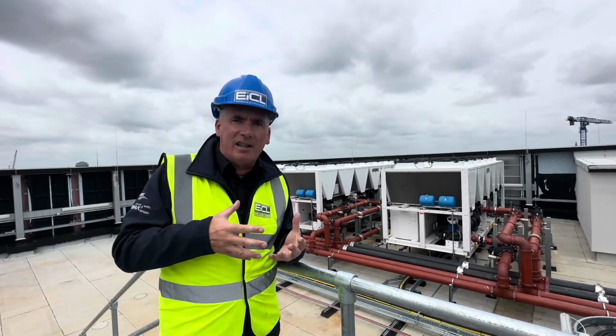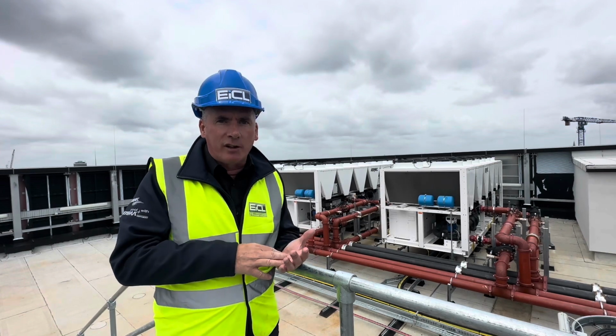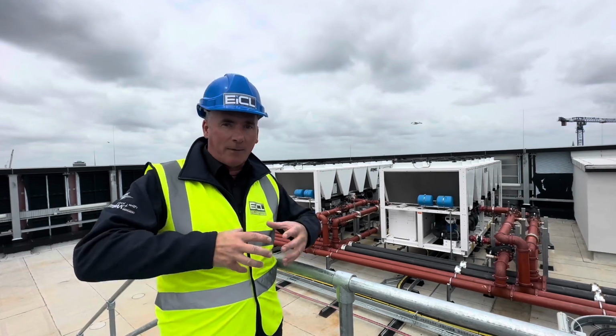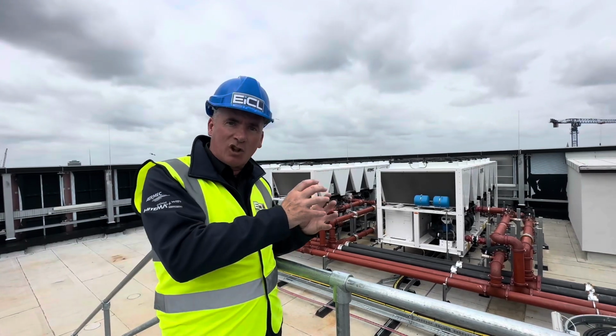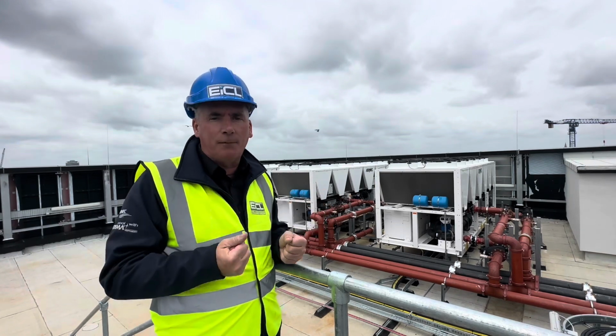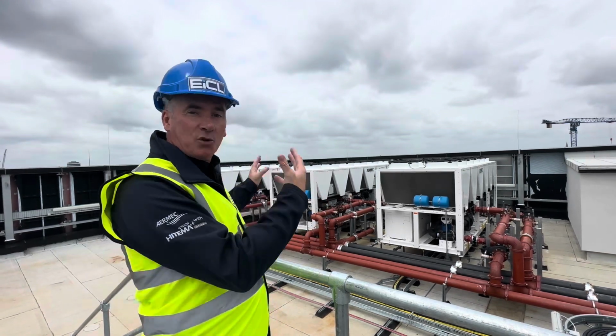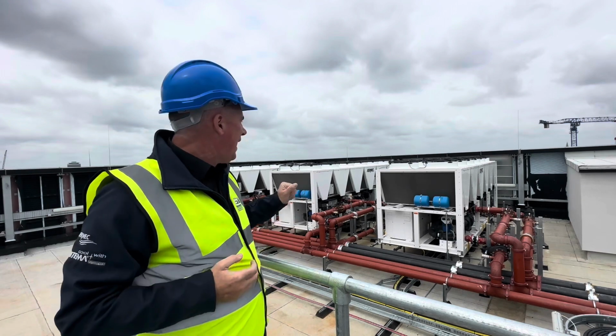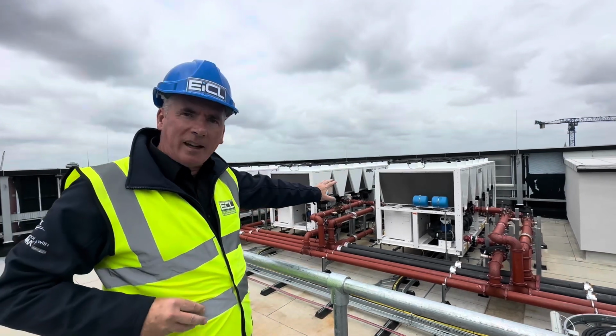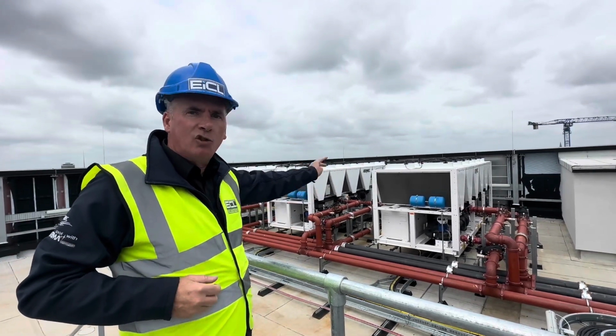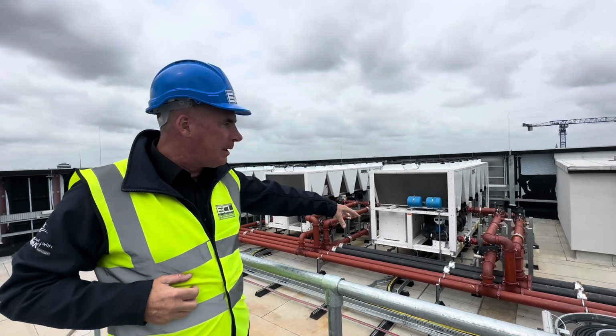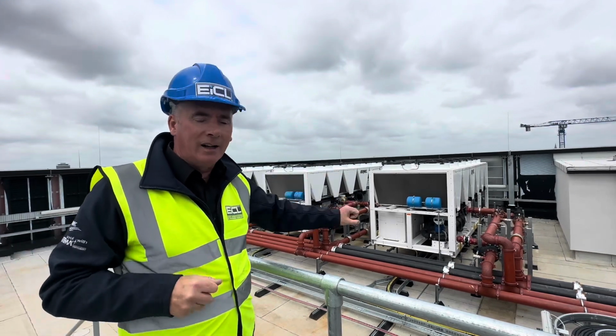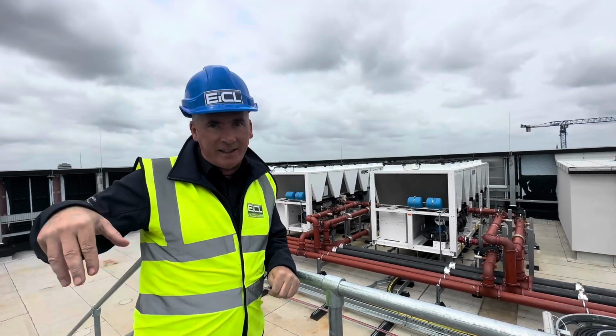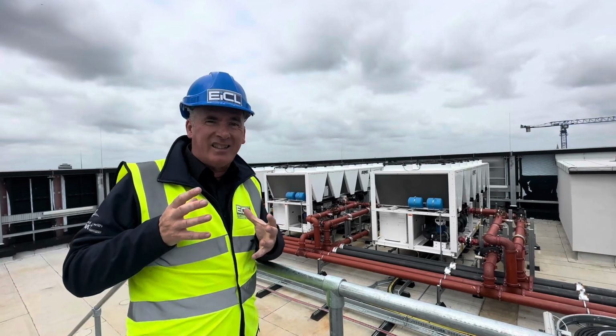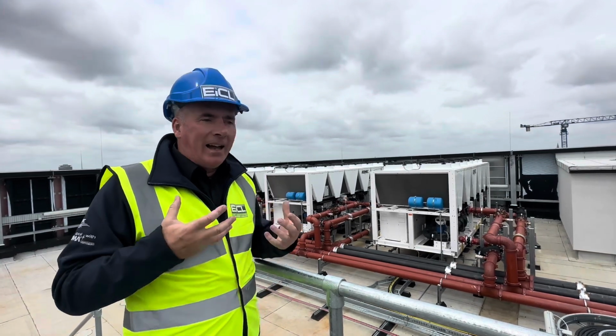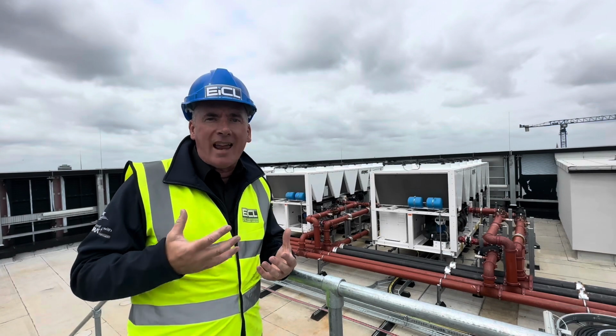A lot of people are used to seeing these on schematics and linear drawings, and we often do schematics where we have a blue beam, where we have the image incorporated, again to try and bring the schematic to life, whereas you can actually physically see what they're like here now. So normally three of them are connected in parallel. You have two pipes for your heating, two pipes for your cooling. They're all married back to your common flow and return header. They will often go to buffer tanks, which you'll see now in the basement in a minute, acting as a decoupling tank. And then the next thing we can do is how we control them.